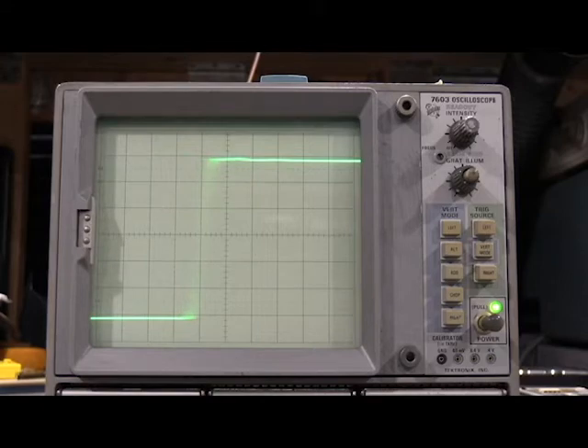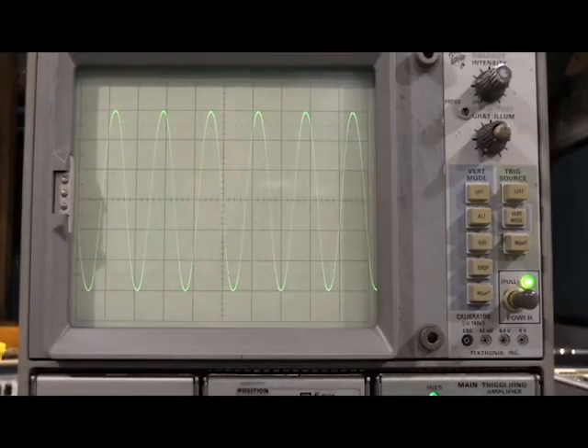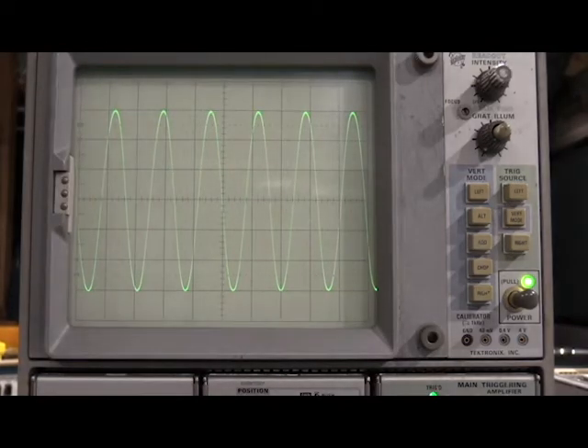Next, we are on to the vertical amplifier bandwidth. The way we've got this started is there's a 3 megahertz sine wave getting fed into the calibration fixture. Frequency response is set, and we've set the amplitude for 6 divisions. So now I have to wind up the frequency until we hit 4.2 divisions. Once we hit 4.2 divisions, that tells me what the 3 dB down point is. So what I'll do now is wind up the signal generator, and we'll see what kind of frequency we're at.